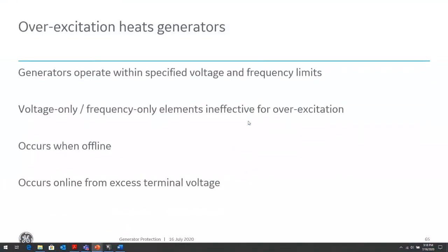Generator over or under fluxing conditions: overfluxing, or overexcitation, can be caused when the AVR, the automatic voltage regulator, has a problem, such as a blown fuse. The machine is slowing down, so the frequency is reducing, and we basically have an excitation above the limit of the machine. In terms of voltage, light loading causes the system voltage to rise and frequency to decrease. Incorrectly switched caps and reactors can cause this, as can excitation boost from loss of nearby generation, with low frequency at these elevated voltages.